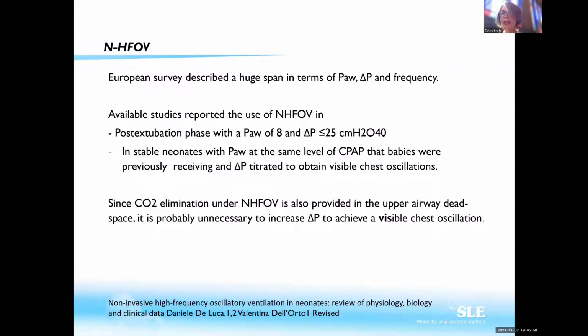What the studies have shown is that when we look at the electrical impedance, we see that part of the tidal volume will go to the lung, and the distribution of the tidal volume when we do an HFO is also more even in the lung. So here you will set your MAP like a CPAP. It means that if you have a problem of oxygenation, it is the MAP or the FiO2 that you will change. The delta pressure won't affect anything. And then if you have some problem of ventilation or of CO2 which is too high, for example, you will increase the delta pressure.